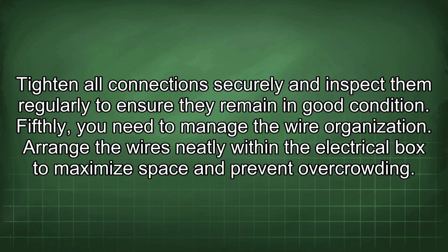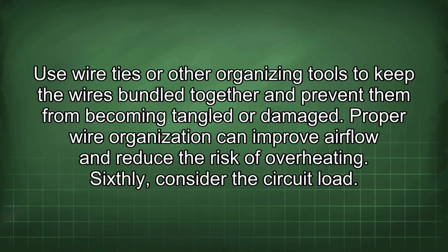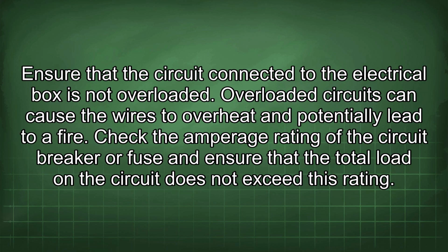Fifthly, you need to manage the wire organization. Arrange the wires neatly within the electrical box to maximize space and prevent overcrowding. Use wire ties or other organizing tools to keep the wires bundled together and prevent them from becoming tangled or damaged. Proper wire organization can improve airflow and reduce the risk of overheating. Sixthly, consider the circuit load. Ensure that the circuit connected to the electrical box is not overloaded. Overloaded circuits can cause the wires to overheat and potentially lead to a fire.